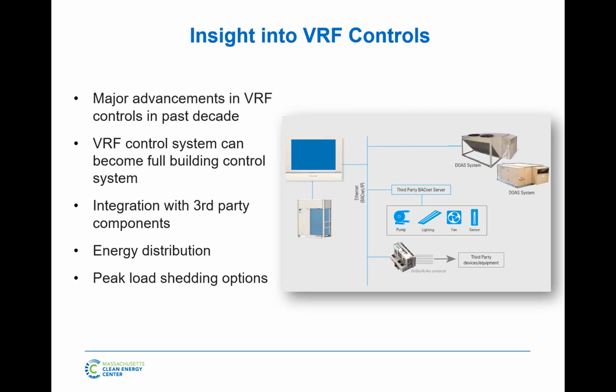So the question is, the peak shedding is not done on an amp draw? So no, that's a good question. With the peak shedding, it's a percentage of use. What doesn't exist, you could program it externally. What doesn't exist is, here's an amp meter, and when I close this contact, that meter can't go past 18 amps, for example, which would be useful for generators and all that. So you have to program around that a little bit. Okay, I'm going to go to 40% or 50%, so it doesn't use amp draw. It does it as a percentage load, the percentage compressor run. You would have to back calculate that to amps.